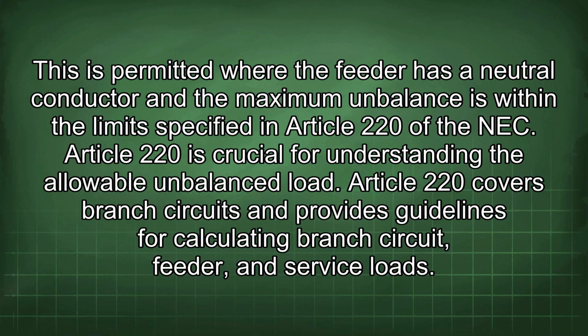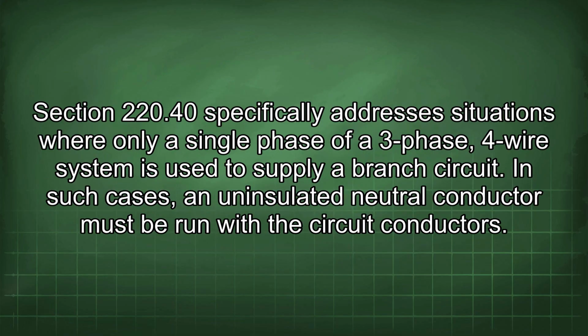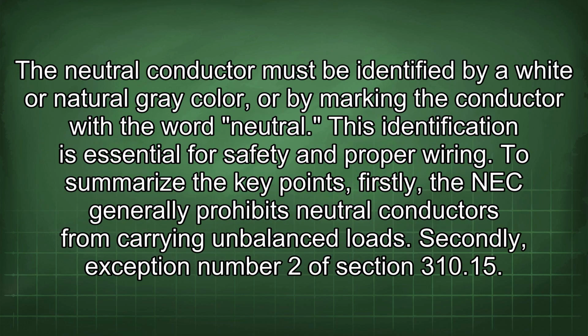Article 220 is crucial for understanding the allowable unbalanced load. Article 220 covers branch circuits and provides guidelines for calculating branch circuit, feeder, and service loads. Section 220.40 specifically addresses situations where only a single phase of a 3-phase, 4-wire system is used to supply a branch circuit. In such cases, an uninsulated neutral conductor must be run with the circuit conductors. The neutral conductor must be identified by a white or natural grey color, or by marking the conductor with the word neutral. This identification is essential for safety and proper wiring.